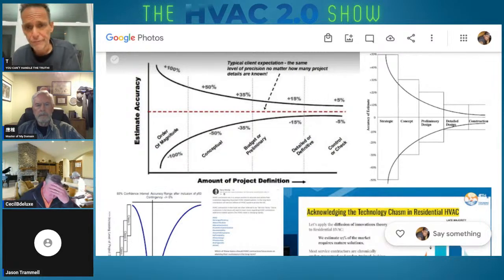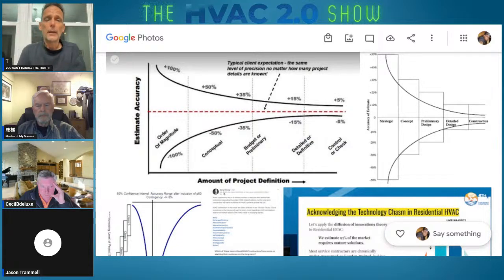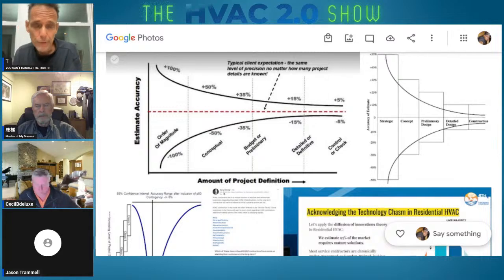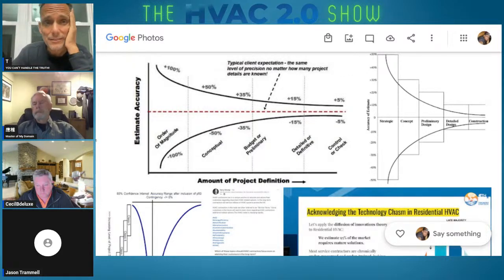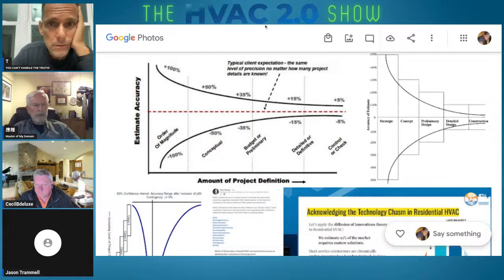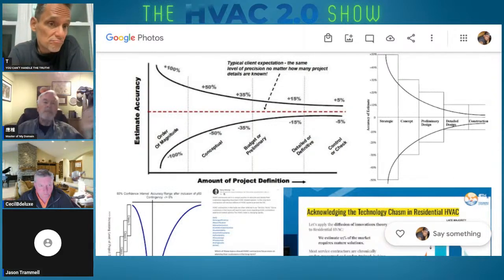And one of the things that we found from all of these guys at Williams that were doing duct analysis is that if you go to a duct analysis and match the ductwork to your oversized equipment, oftentimes that doesn't solve the problem either. Just like tightening a house with oversized equipment can make the house more uncomfortable, oversized ductwork can do the same thing. Do you guys want to talk a little bit about that? I would have to get a better definition of oversized ductwork. Well, let's say upsized ductwork.